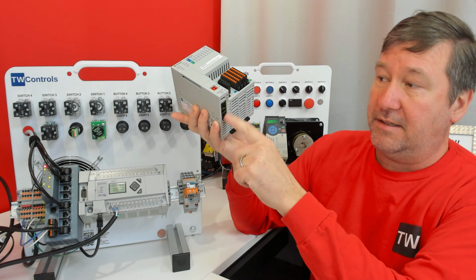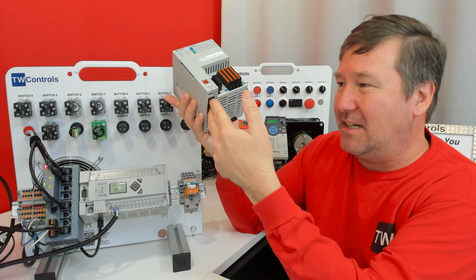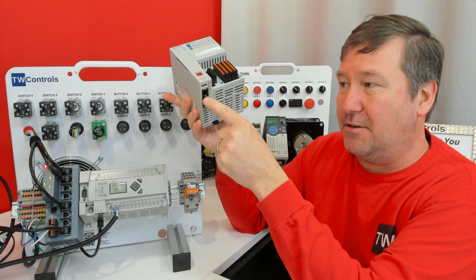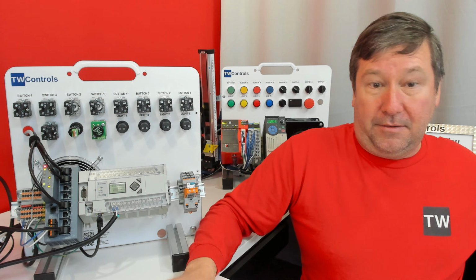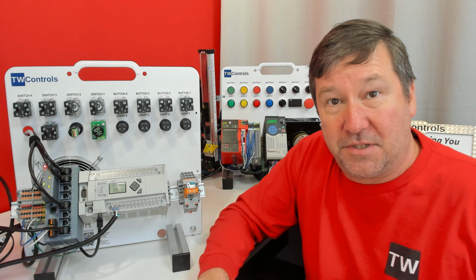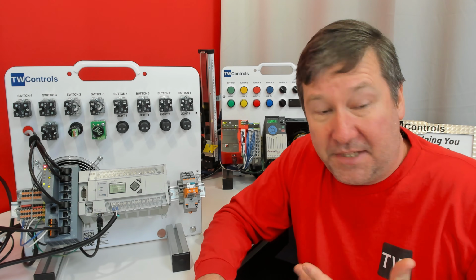And I'm used to, here's what I was getting ready to do, I was going to enter 2, because this is what I know with all of the regular CompactLogix PLCs. So in the case of our L16, it's really arguably just a built-in Ethernet switch. And so either one of these is 2 going out. Now, this one can be configured, its individual ports can be configured separately or together.